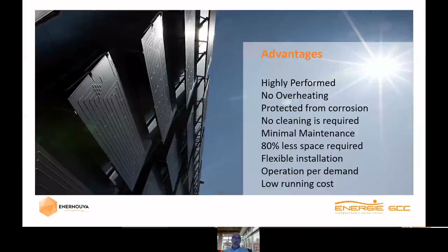One important feature about our system is on our biggest systems that we provide for residential towers, hotels, hospitals, staff accommodations. We monitor our performance, and we do it in a very transparent way because we install meters to measure the electrical consumption, the water flow, and the temperatures, and we share all this information in real time with our clients. They have a dashboard, and that allows them to see and to have more information and better data that will lead to a better energy efficiency system. At the same time, it gives transparency in terms of the relationship we have with the client, because when we propose something to the client, it's based on real information, and they can actually see it when the system is operating.